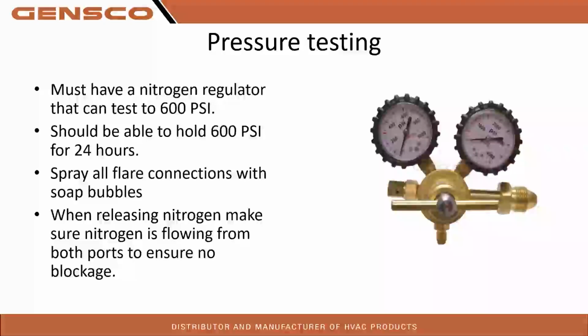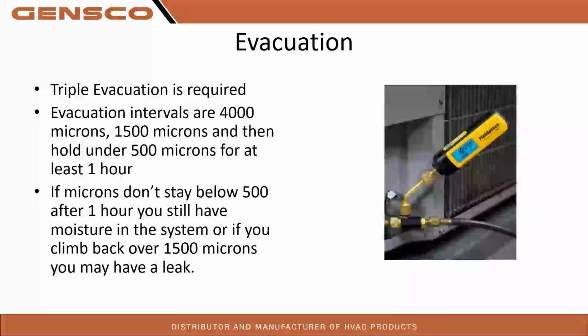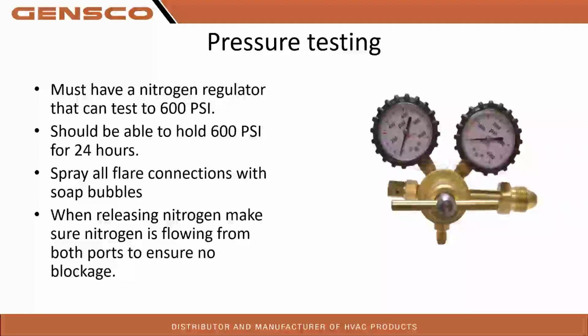Hey Garrett, can I mention something on this slide? Yeah, absolutely. What do you got, Chris? So I was going to mention that if your nitrogen gauge says 600 psi, a 600 psi gauge regulator, it is not going to get your system up to 600 pounds. So make sure your regulator is capable of at least 650. That way you can get 600 psi out of it.